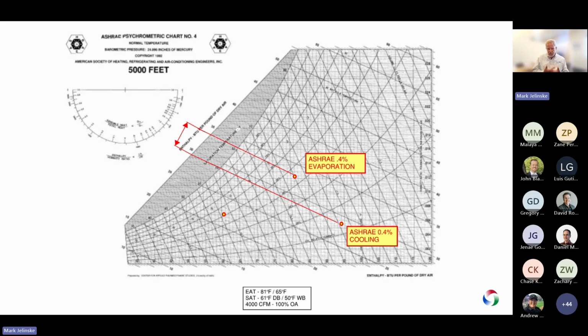However, this is a 100% outside air unit. So when I look at the other value, the ASHRAE 0.4% evaporation value, that's showing in our climate that even though the dry bulb temperature is lower than the dry bulb temperature of the typical cooling value used, the energy level is higher than that. So in order to decide what the worst case design conditions are going to be, we've got to use the higher energy level.